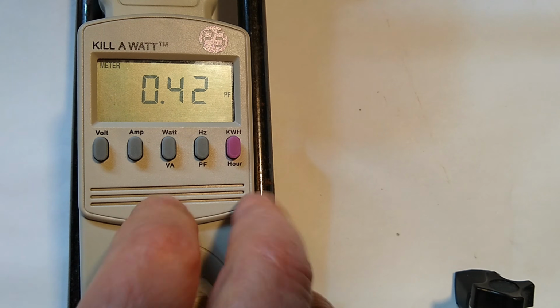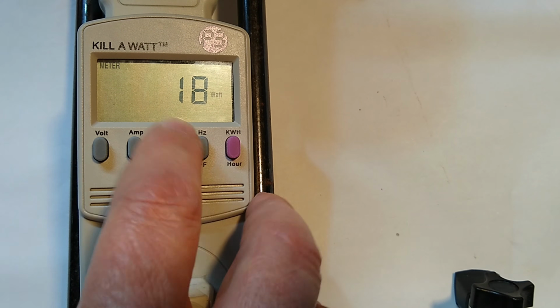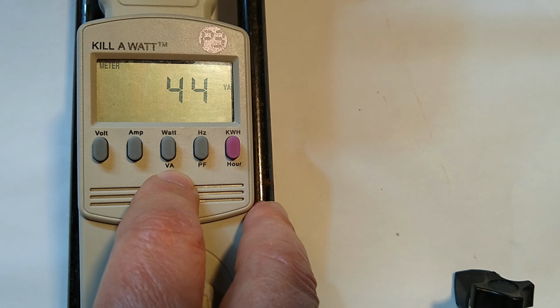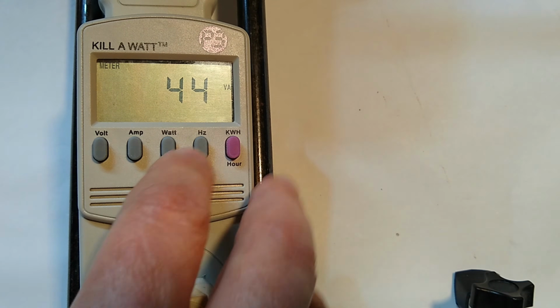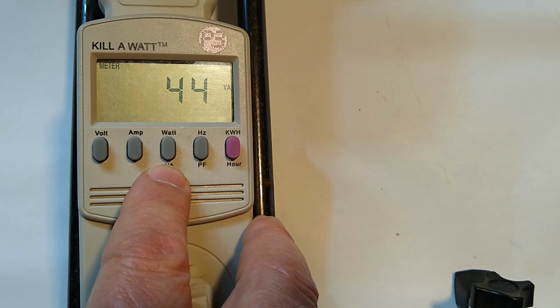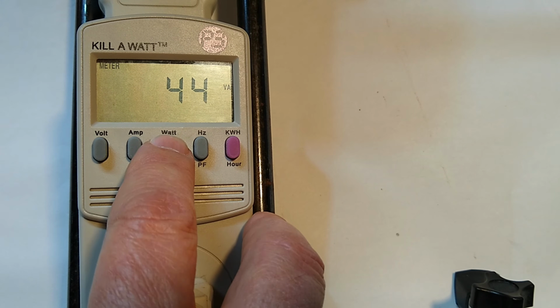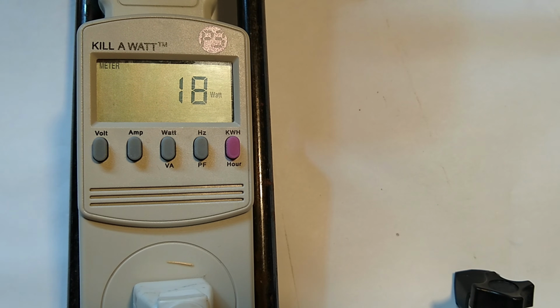So if you notice, if you take the 0.42 and multiply it times 44 volt amps, it's teetering 43, 44. Multiply it times 44 volt amps, and that comes up very close to 18 watts. It's actually around 18.5 watts.